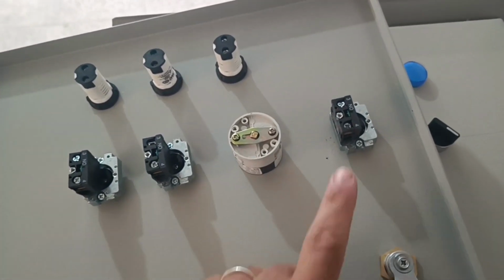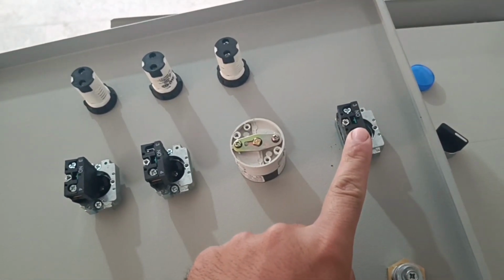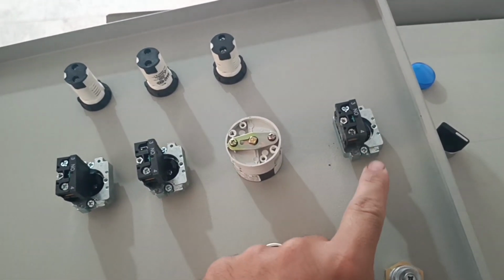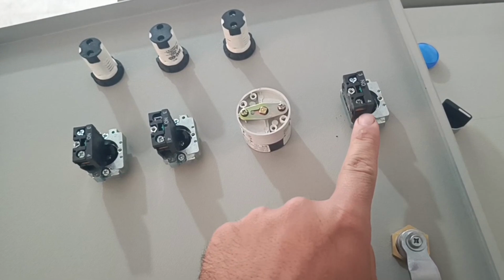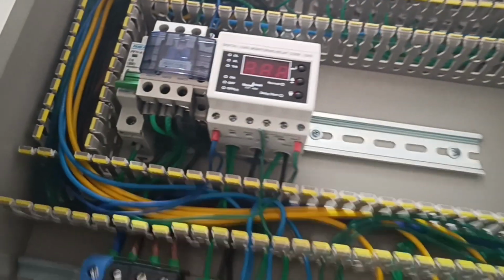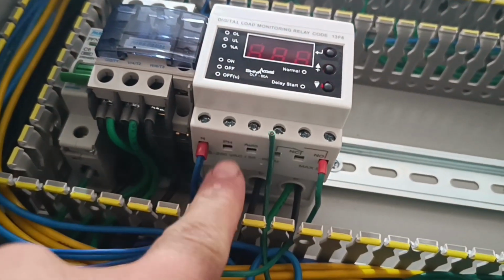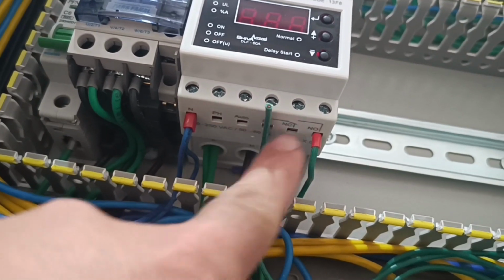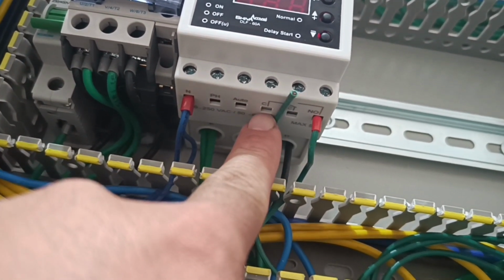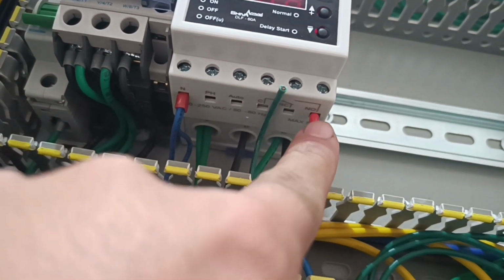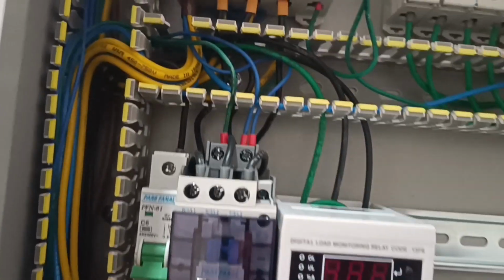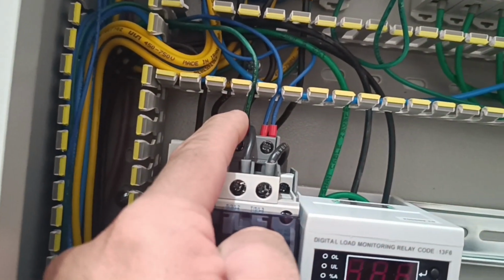This switch is used for turning the three-phase contactor output on and off. The input of this switch is connected to the output of the phase controller relay labeled as 18. The output of this selector switch is connected to the input of the phase controller relay, which is labeled as PH and C. Then from its output labeled as NO, normally open, we connect the coil of the contactor.